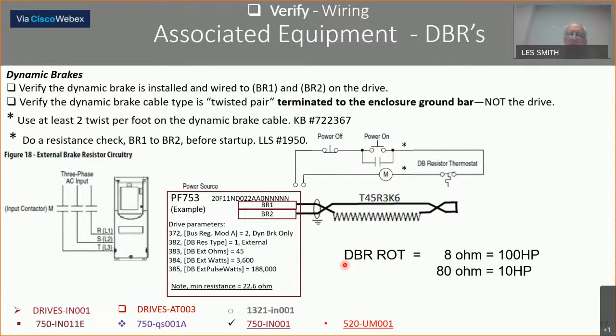For instance, let's take a look at ours. We have 45 ohms. This is a 15 horsepower drive. And if you look at the nameplate or look it up, the minimum resistor on this is 22.6. If a motor can brake 150% up to 200%, you're going to see that reflected in this resistor. This resistor is roughly half of what the 80 ohm is. So we got about a 20 horsepower braking torque on this resistor. So you can see resistors out there and you can just estimate. And this is just a rule of thumb that you can be quicker on your feet out in the field.